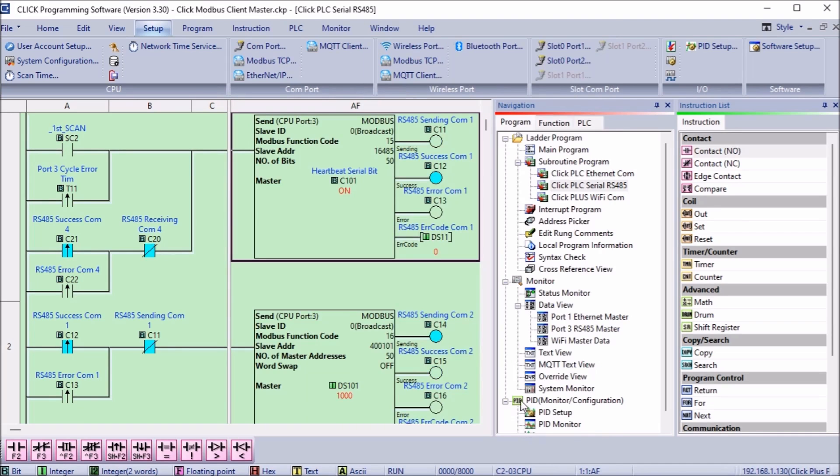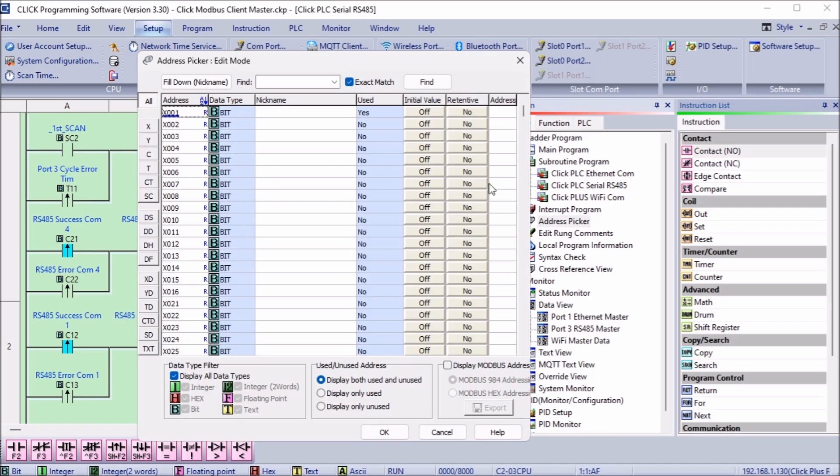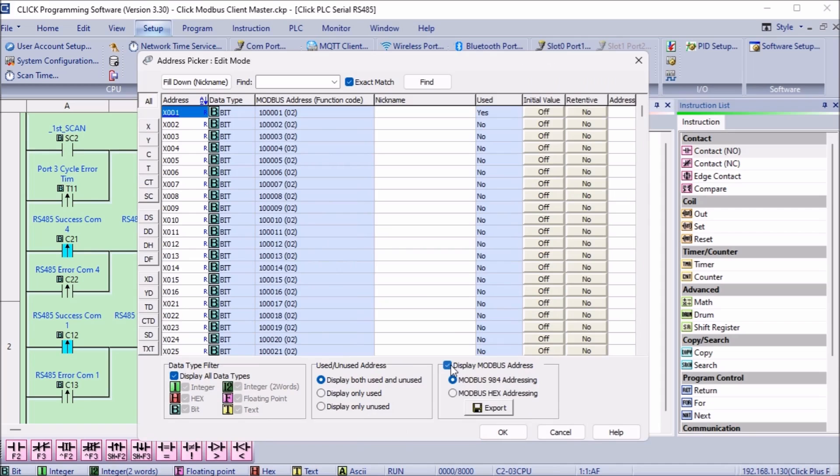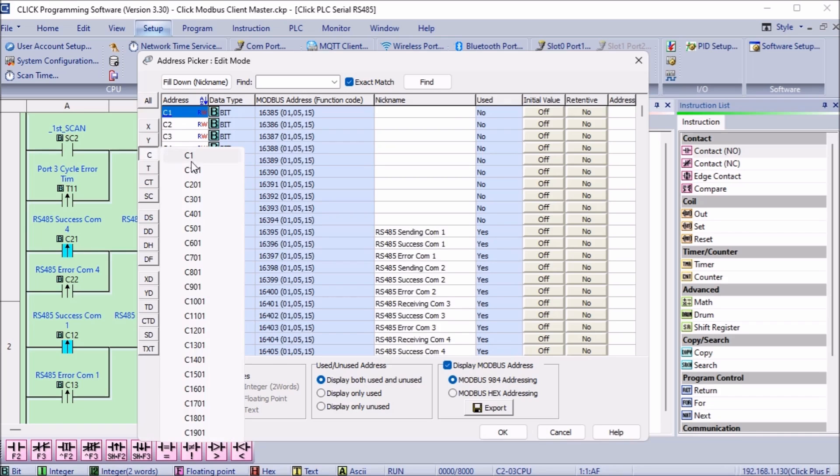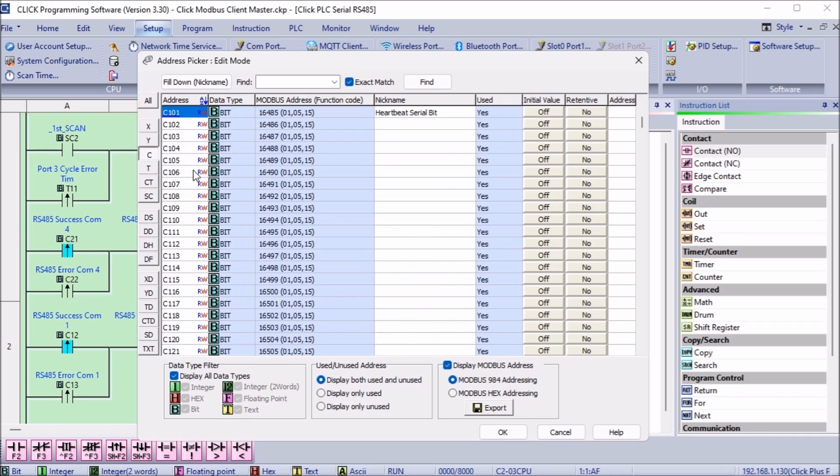Call up the address picker from the main menu program. Select display Modbus addresses in the bottom right side of the address picker window. This will display the Modbus addresses for all the memory locations in the Click PLC. You will see that 16485 is the address for C101.